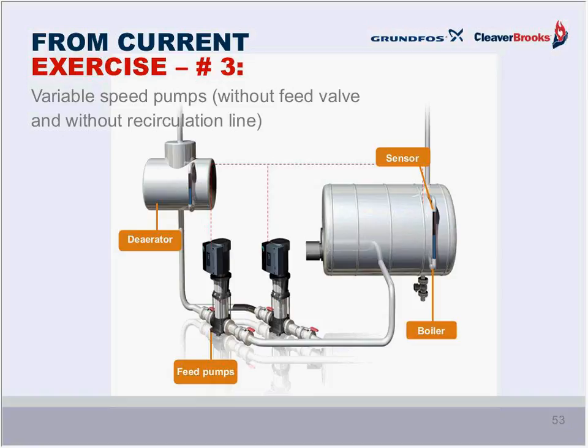without a feed valve. There's a sensor on the boiler, and that's directly feeding data to the control on the variable speed drive, to speed up and slow down the pump to match the flow rate to the needed water level in the boiler. There's no feed valve. That adds a lot of head to the system, so getting rid of that is good. And there's also no bypass line. Both of those are going to help in reducing costs and power consumption. And there are additional variable speed benefits of power consumption, as you're going to see here in just a minute.